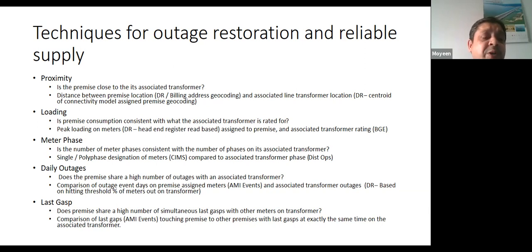Suppose R phase is 200% loaded, we can say put some consumers from this phase to that phase, or maybe one pole taking from R phase can be switched to Y phase, so that balancing of power happens. This also requires an algorithm to identify the phase. Similarly, by looking at alarm patterns, we can know that a transformer is always giving voltage alarms, maybe due to a winding problem or an overloaded transformer.